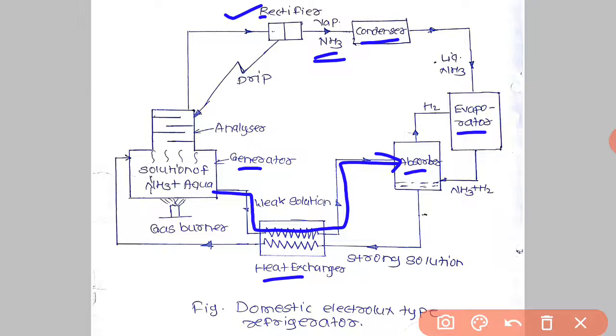The liquid refrigerant leaving the condenser flows under gravity to the evaporator, where it meets the hydrogen gas. So the condenser is cooled and vapor ammonia is converted into liquid ammonia, and then it will meet the hydrogen in the evaporator. The hydrogen gas which is fed to the evaporator permits the liquid ammonia to evaporate at low pressure and temperature according to Dalton's principle. During this process of evaporation, the ammonia absorbs the latent heat from the refrigerated space, and the cooling effect is produced in the evaporator. So the refrigerating effect or cooling effect is produced in the evaporator.